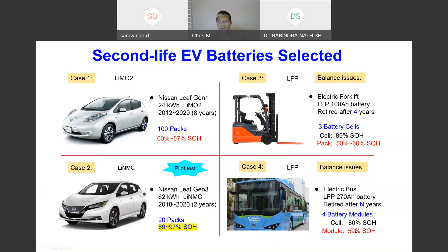The last type of battery we tested is from an electric bus, which is a 270 ampere-hour battery. They are retired after about 4 years. And these battery modules, at the cell level, maintain roughly 80% of their original capacity. But at the module level, the capacity is only 52%. Therefore, these batteries also have a huge balancing issue.